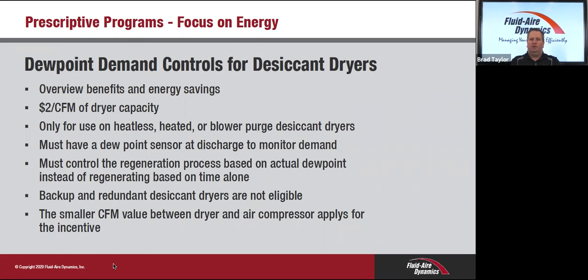You've got two chambers full of an adsorbent, controlled by switching valves, which are obviously controlled by a timer. That timer will just cycle those towers back and forth regardless of the dew point level of your compressed air. Now, desiccant dryers consume about 15% of your compressed air to regenerate those adsorbent beads. So that's reducing the capacity of your system, but it's also consuming a bundle of energy.